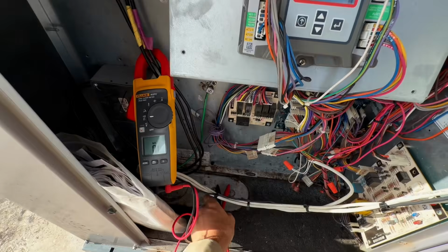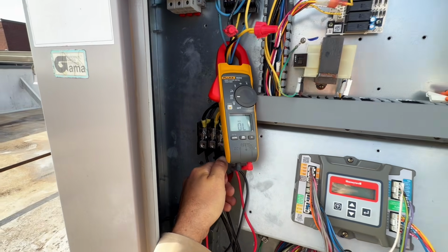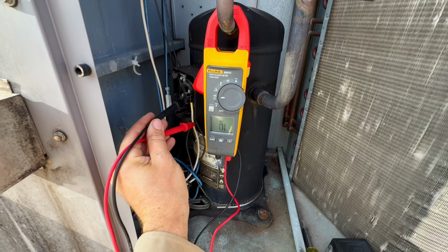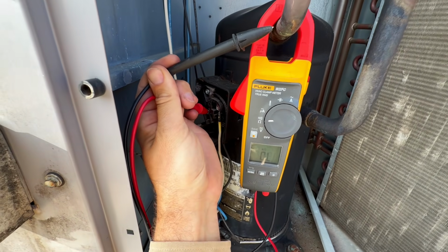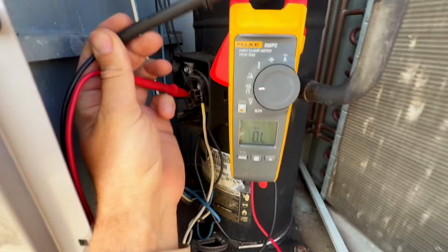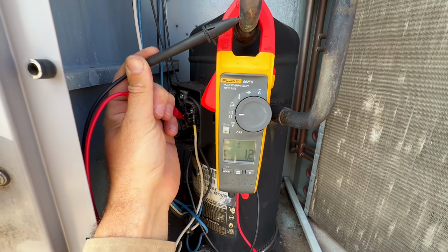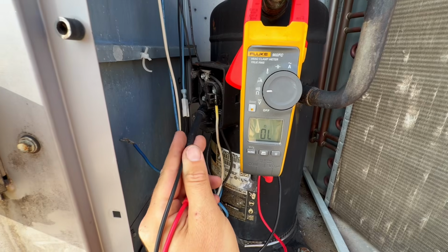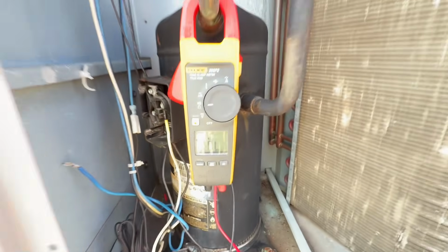Now let's go back over here. What do you know? No connection to ground. And now to confirm, because I always like to be 110% sure about my troubleshooting diagnostics, let's check here. And you can see this is our resistance to ground. We have nothing connected over here, so this is definitely our issue going on over here.